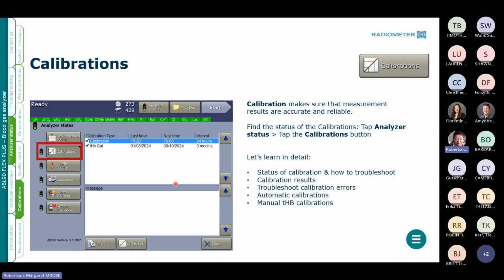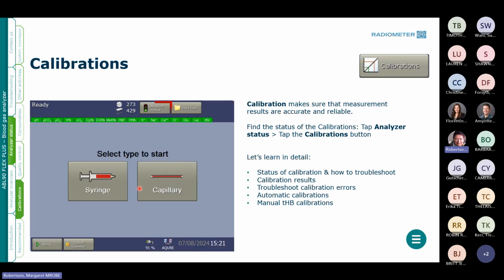Calibrations on the analyzer. There are several calibrations on the ABL90. The first is the routine calibration, which is the main analyzer calibration, and also the THB, or total hemoglobin, calibration. One is automatic, built into the system, and the second one, THB, actually has to be accessed and calibrated.